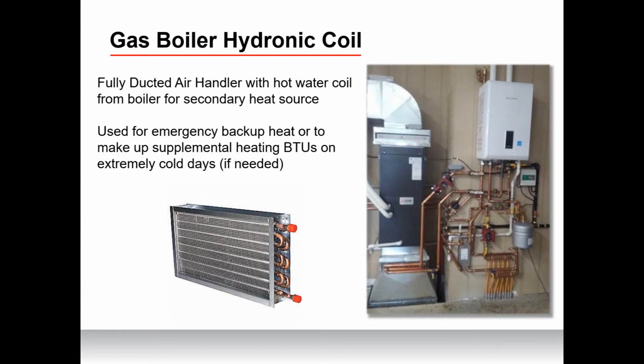Our current solution that's becoming more common though, even with our existing equipment, is the use of hot water coils on fully ducted air handlers as a secondary heat source. This allows the use of a gas boiler for domestic hot water and secondary space heating when tied with an air source heat pump. The hot water coil would be a third-party source product, sized appropriately for the heating need and CFM static requirements of the area.